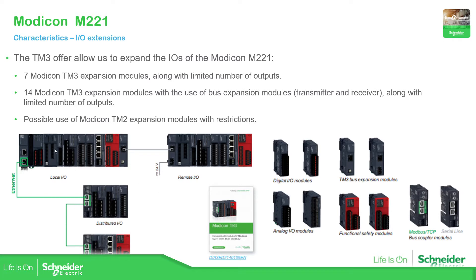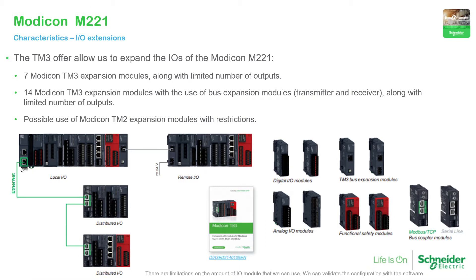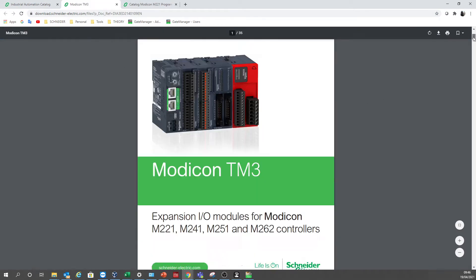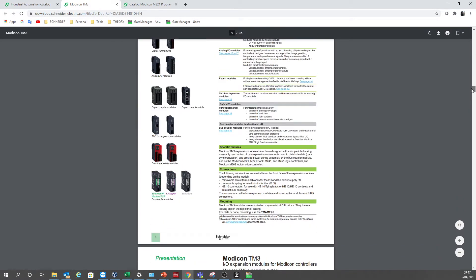The TM3 modules are placed on the right side of the PLC, and you can connect up to seven. You can then use a transmitter and receiver to extend from 7 to 14, depending on the actual PLC model. We can also use Ethernet or Modbus serial to extend using the bus coupler. More information about TM3 models is available at se.com; navigate to PLCs and all controllers, then select the Modicon M221 to see the PLC catalog and TM3 catalog for the complete expansion solution.